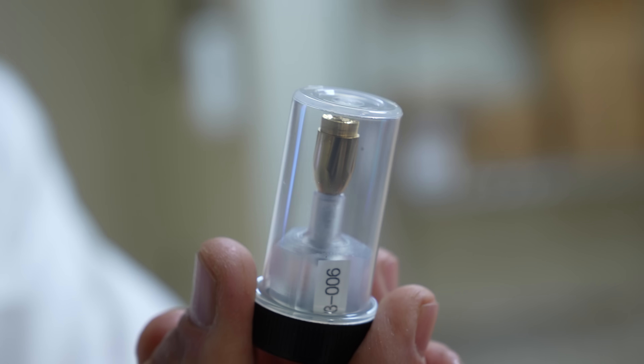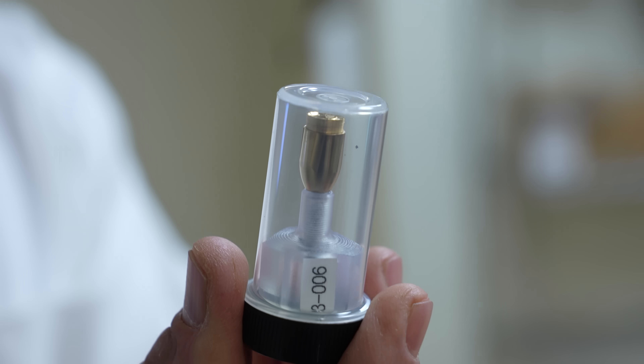This has standard marks on it. They replicated a bullet, putting essentially nano indentations on it — very, very fine marks — and have mapped it on this bullet. They weren't fired through a gun; they were manufactured. So to validate their equipment, forensic labs can run the standard bullet at the same time as a bullet from a crime scene, so they know their measurements are accurate.